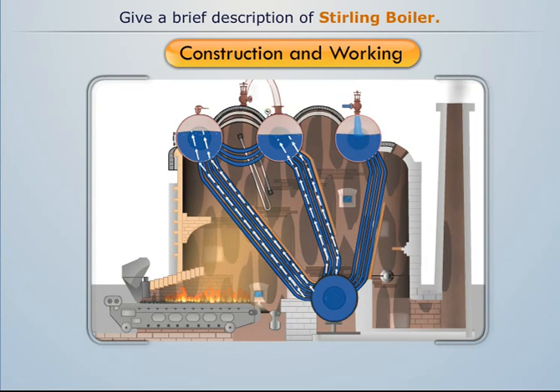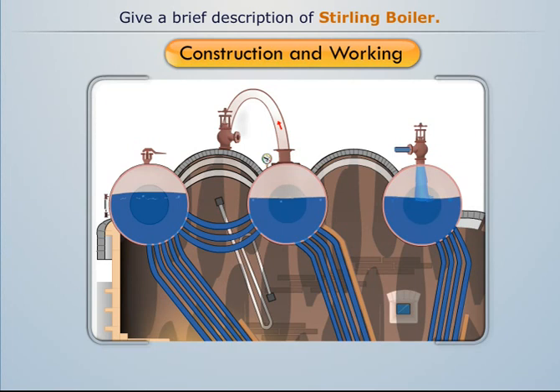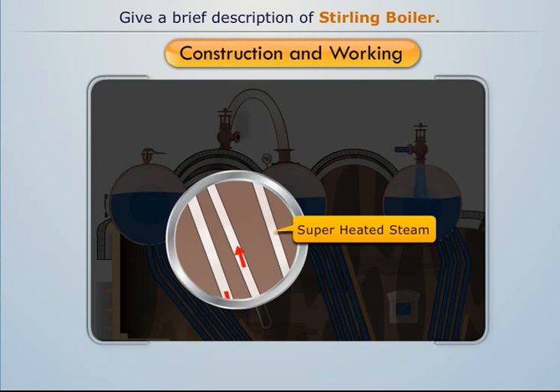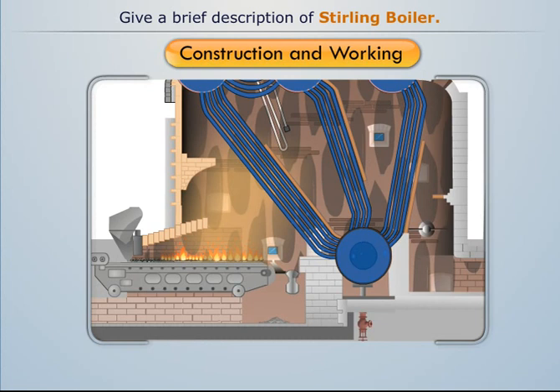The steam moves upwards and gets collected over the water level in the steam drums. Saturated steam is extracted from steam drum 2 and supplied to the superheater tubes. This converts the saturated steam into superheated steam, which can be taken out from the steam stop valve.